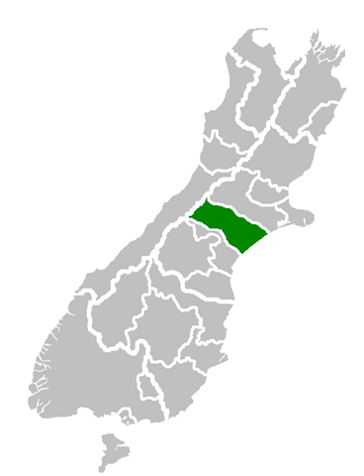In the late 1980s and early 1990s, Transpower, then a division of the Electricity Corporation, went about a rationalization of older transmission lines in the South Island, and as a result dismantled the 110 kV lines between Hororata and Temuka which supplied Ashburton. As a result, a new 220/33 kV grid connection was established in 1992 under the Islington, Bromley to Twizel 220 kV lines at Elgin, 7 km southeast of Ashburton Township, to supply the AEPB network in the Ashburton area.